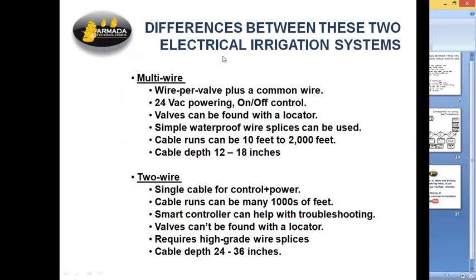I've made a bullet list here of the differences between a multi-wire and a two-wire system, listed the multi-wire and then the two-wire. I won't read the list of bullets, but you get the idea of the difference between them. The two-wire system has a single cable with two wires in it for control and power that daisy chains all the valve boxes together, whereas the multi-wire, what you're more familiar with probably, has a wire per valve with a common wire. So that's a pretty fat bunch of wires.